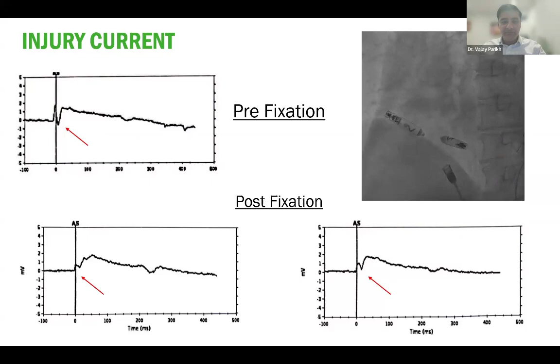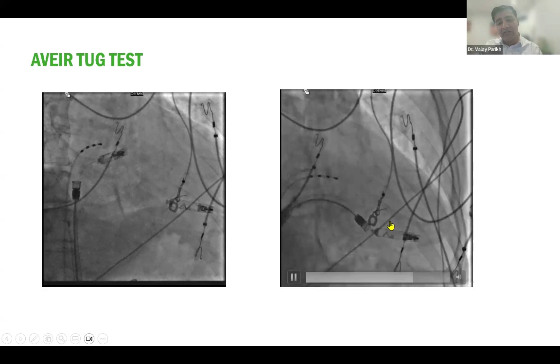Before we release, just like the Micra device, we can do a similar tug test for Aveir devices as well. Here we don't have tines, but what we are looking at is the stability of the device when we do a gentle tug, and seeing if the device is freely floating or it's caught in the myocardium. So this is for the atrial device. We want to reduce the appendage movement, and that way we can see if the device is stable. Similarly, for ventricular devices, we can see that. In addition, sometimes we do something called a flexion test, and by flexing, we are moving the proximal end of the device while looking at the chevron and the distal end to make sure that they are attached to the myocardium and stable.